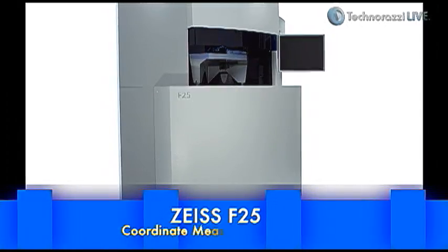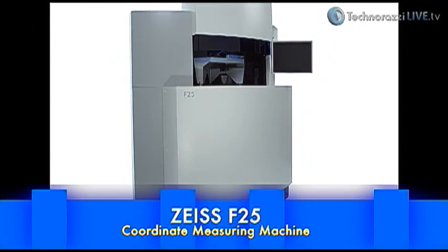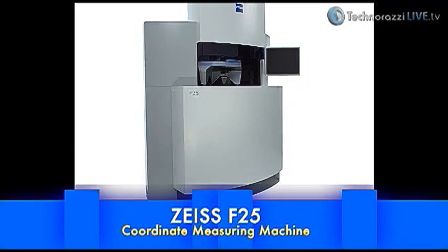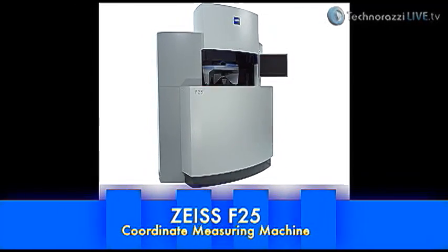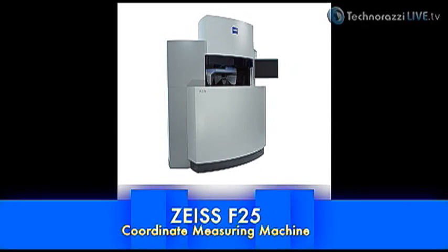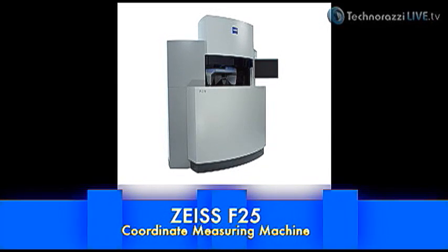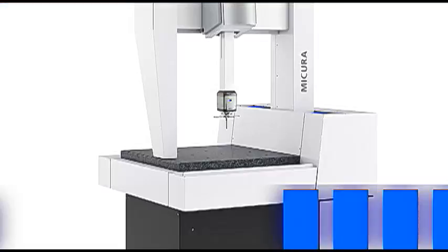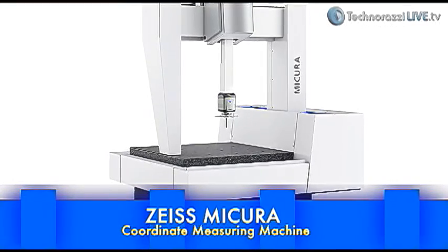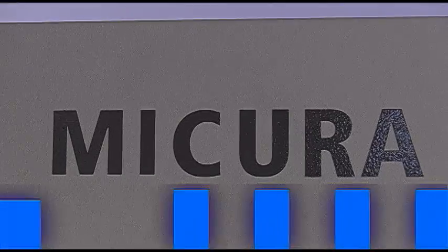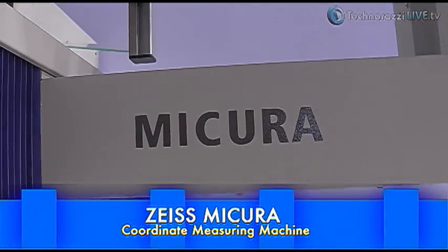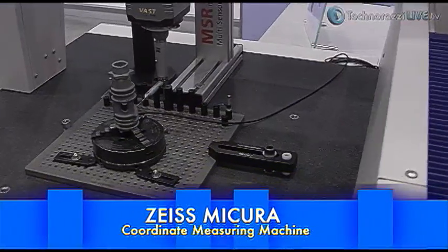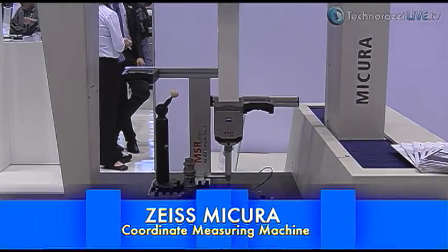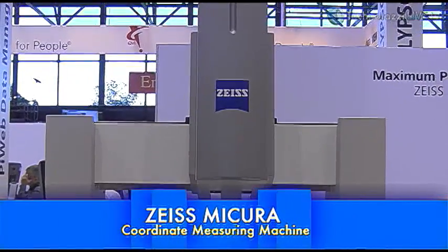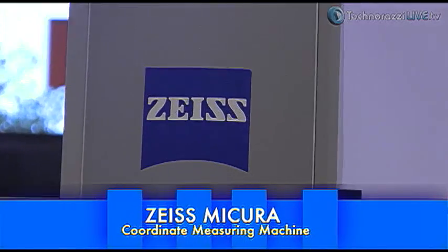Accuracy. Wow. And are these small volume machines or larger volume? The F25 is a 4-inch measuring volume, so very small, and it was purposely designed for doing micro-machined components. So think watch components, things of that size or smaller. The Micura is a much larger machine, but let's say for very accurate tooling where the tolerances are in the 1.5 to 2/10 range, and you need a piece of equipment that's better than that for doing the inspection. So 20, David, correct me if I'm wrong, 20-inch cube roughly on the Micura? 500 millimeters, 500 millimeters, 500 millimeters. Okay. Fairly small volume. Well, 20 inches actually isn't all that small.